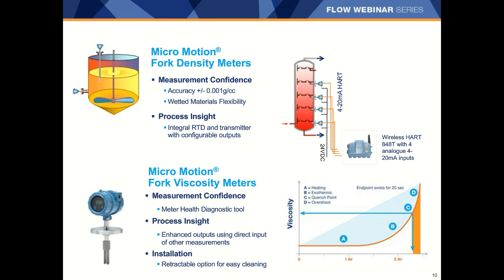A good application may be in multi-stage reactors or columns, where oftentimes feed composition represents a significant upset to production. For systems where composition can be determined using density, density meters to monitor the feed in various stages throughout the column can help better control the efficiency of the equipment. Additionally, the internal RTD allows you to take temperatures at each stage for reaction profiling. Using WirelessHART technologies to pull off those extra variables can be an affordable way to add automation to your process.